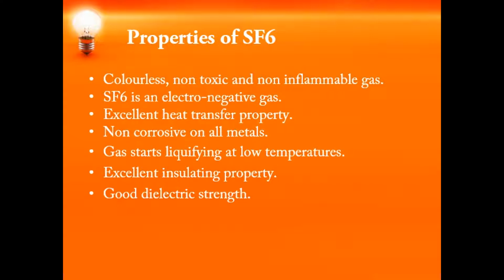At atmospheric pressure, its dielectric strength is around 2.35 times that of air, and at 3 atmospheres pressure its dielectric strength is more than that of transformer oil. So compared to air and oil, SF6 has a very good dielectric strength. Next, it is an electronegative gas. Electronegative gas means it has a high affinity for electrons. The electrons are attracted very fast.